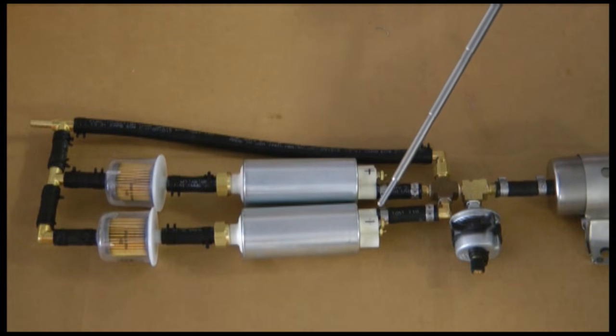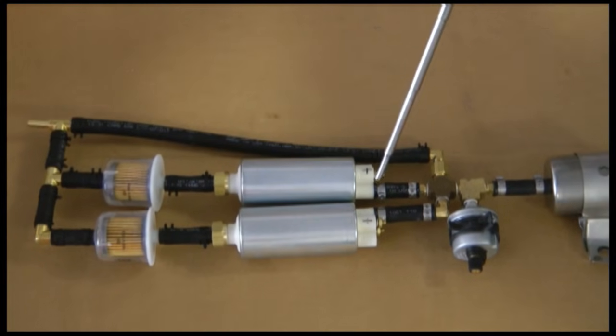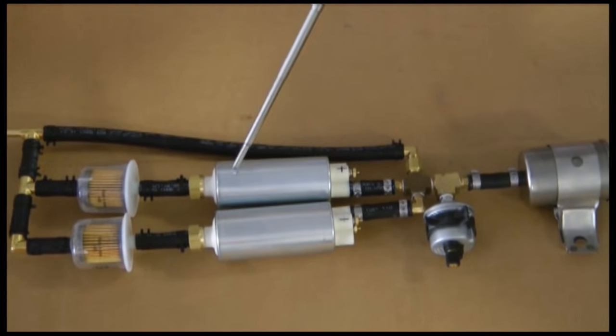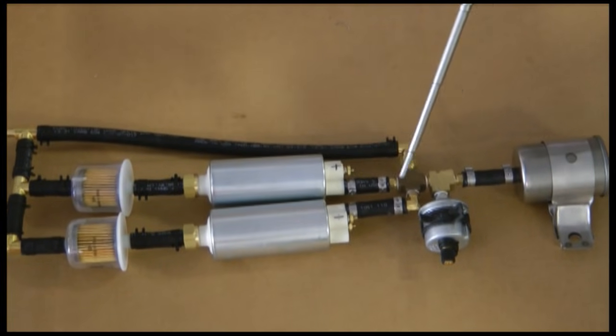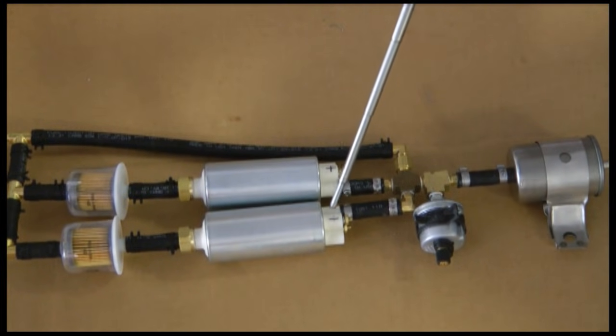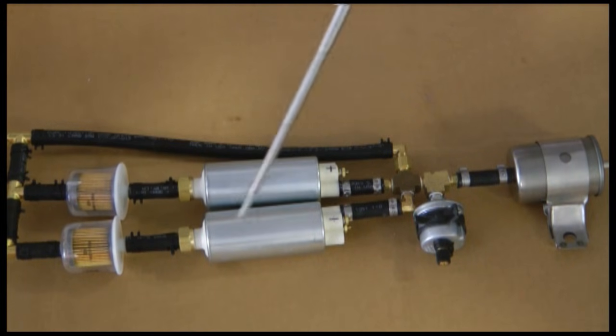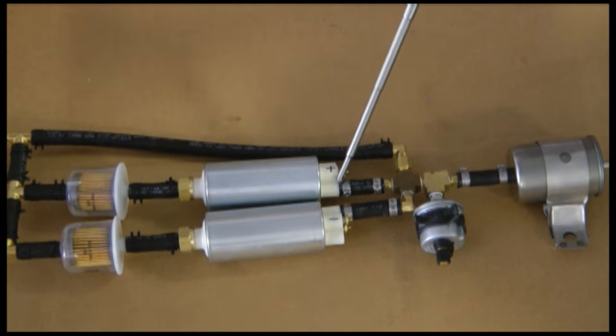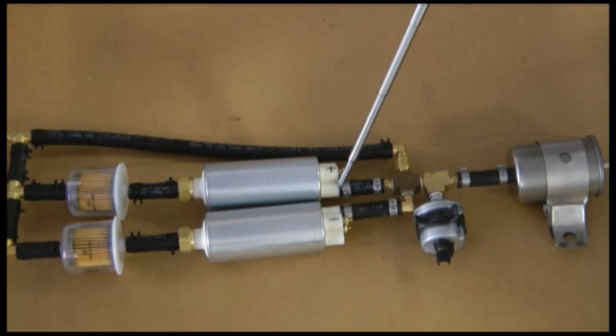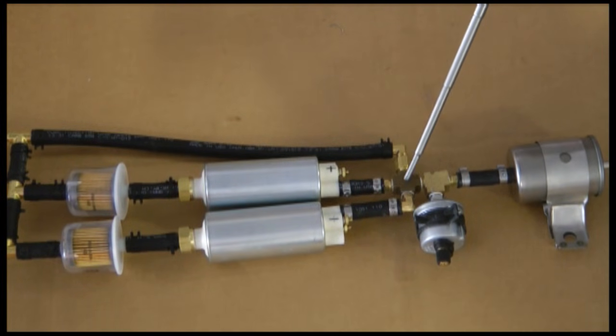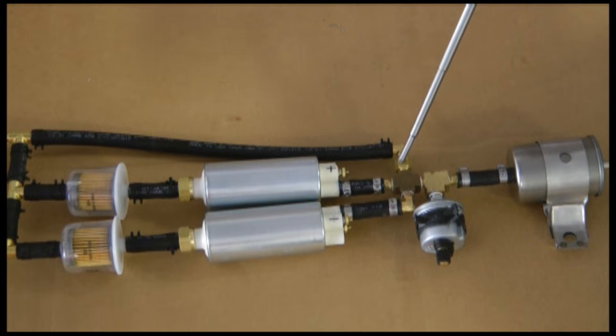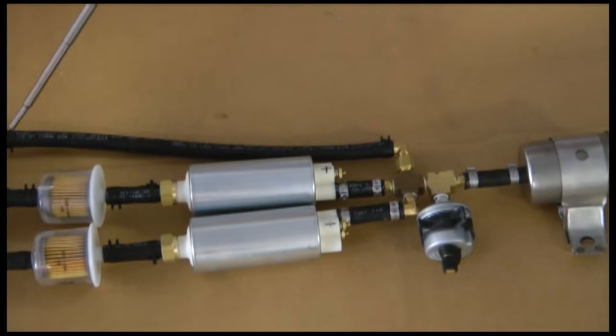The outlet side of the fuel pumps have built-in check valves internal to the pump. So fuel that is being pressurized through this pump body will not be able to flow backwards through the other pump. And the same, if you're using this pump, it will not flow backwards through the opposite pump. Now, some return flow is present. In this area, this brass fitting right here is a reducer. Okay, it is a reducer that brings a very small amount of fuel back to the inlet side of the pumps.